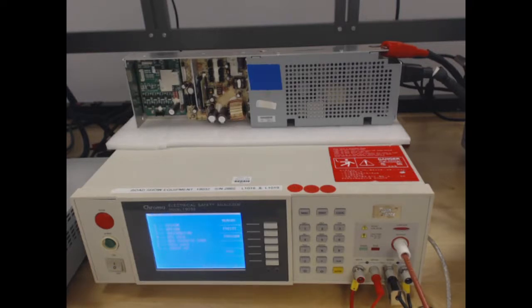There are a few connections involved in setting up the ground bond test. Firstly, the current drive and current sense connections should be attached to the chassis of the unit. Secondly, the neutral should be connected to the ground pin of the AC plug that powers the unit. Lastly, the high voltage terminal can be connected to both the line and the neutral pins in the AC plug for doing high pot testing, although we won't use them in this test.